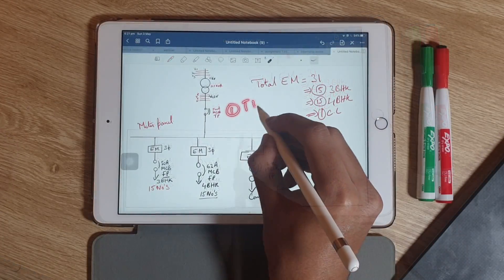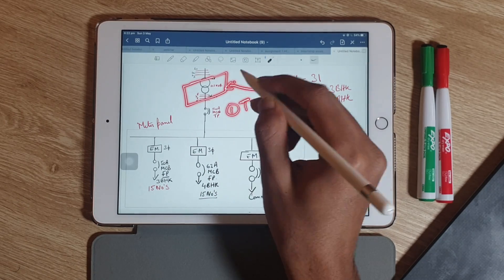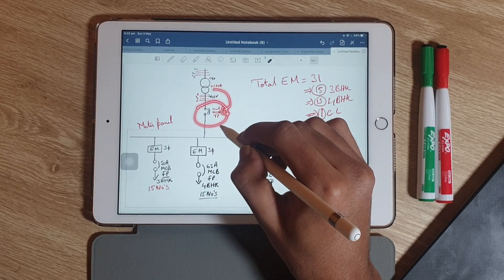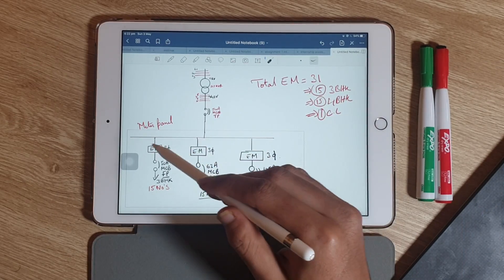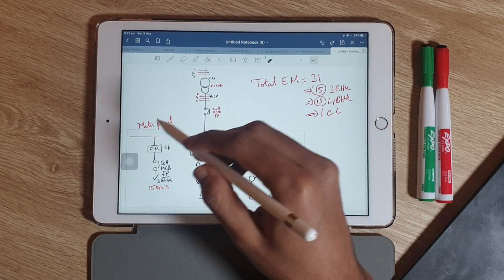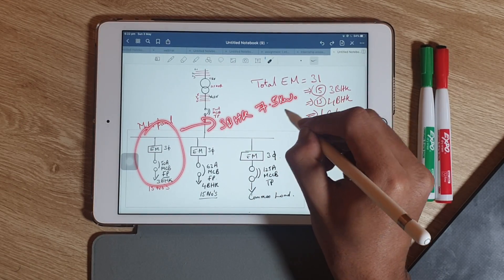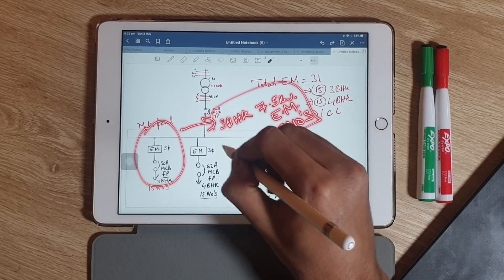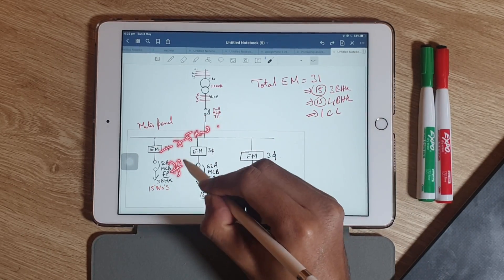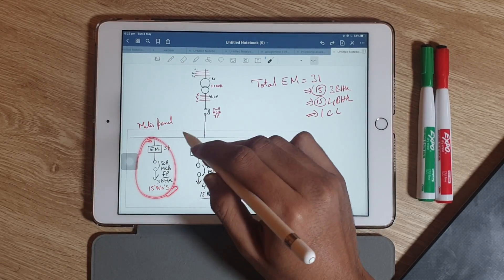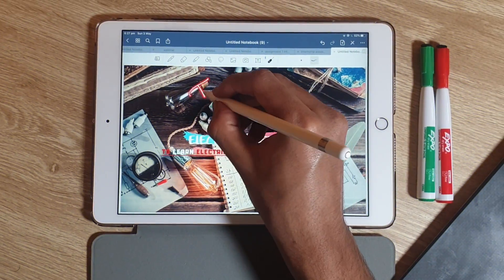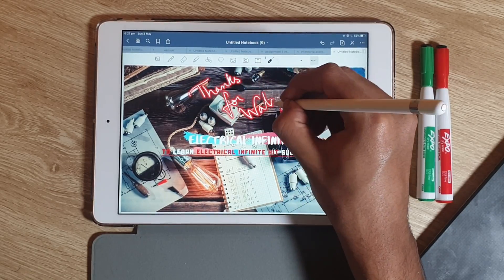To recap: we first calculated the total load, which gave us the transformer size. From the transformer value we derived the main meter panel circuit breaker. Then we calculated circuit breakers for 3 BHK, 4 BHK, and common load. For 3 BHK, a three-phase 7.5 kilowatt energy meter with 15 sets; similarly for 4 BHK. That's all for this video. Hope you found it useful for enhancing your electrical knowledge. Thanks for watching — don't forget to subscribe to Electrical Infinity.